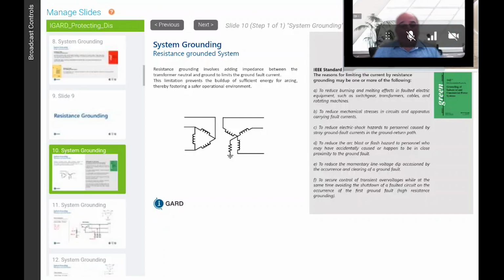I've had this conversation with consultants in the States, and they said that in the States you have 517.17 that basically says you have to have 2 levels of ground fault protection. The only reason to have 2 levels of ground fault protection is that if you have a ground fault and you coordinate properly, you lose much less of your electrical system. Whereas in Canada, specifically Ontario, we have high resistance grounding systems where if you have a ground fault, you don't have to trip at all.